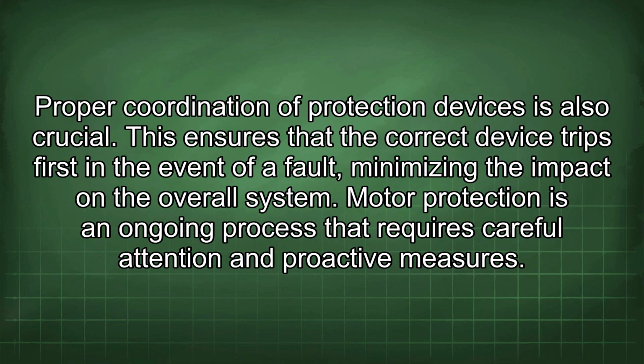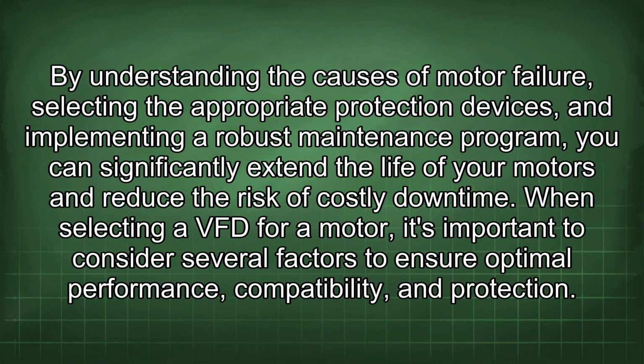Proper coordination of protection devices is also crucial. This ensures that the correct device trips first in the event of a fault, minimizing the impact on the overall system. Motor protection is an ongoing process that requires careful attention and proactive measures. By understanding the causes of motor failure, selecting the appropriate protection devices, and implementing a robust maintenance program, you can significantly extend the life of your motors and reduce the risk of costly downtime.